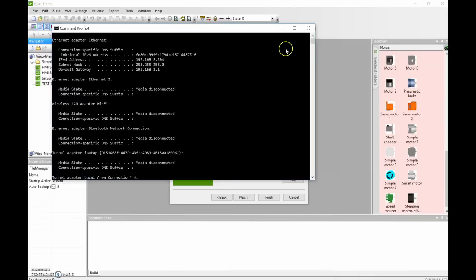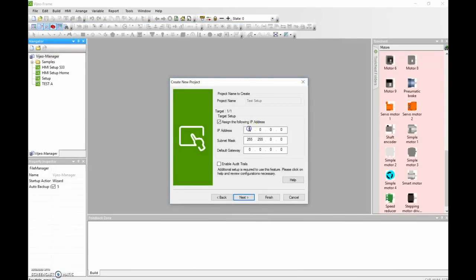So we're going to use those and choose a value that matches so that we can drop it into this Vijeo here. So let's see. I'm going to put 192.168. Then remember it was .2. And then I am consistently addressing my PLC. Sorry, that's my PLC. My drive is 233. My HMI is 232.